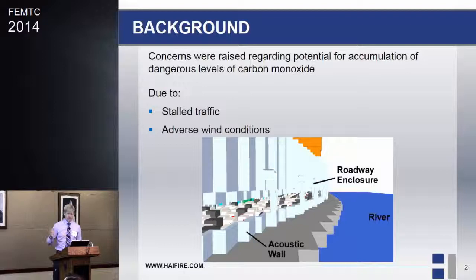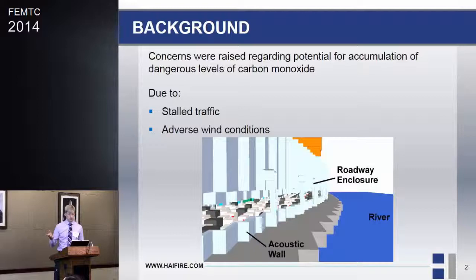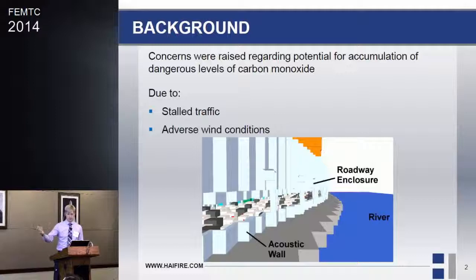Here's a picture of the FDS model. The concerns were raised during the design of this project — buildings will be covering over the roadway, and they were worried that during stalled conditions on the road there could be a significant buildup of carbon monoxide in the roadway, which could be dangerous for the drivers. Due to the river, there's significant wind influence, and we were wondering whether wind coming in from the river and creating a vortex around the opening could cause problems.